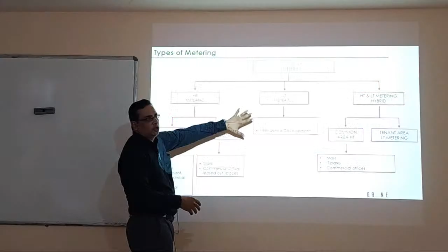I am getting my feed from outside from a supply company. I am only putting meters. I am not putting transformers inside. Much simpler for you. You don't need to give a space for transformers. But when you shift from a residential development to a commercial development, which is a mall or a hotel or a hospital or something else, you will go into this category. So it's called HT metering. HT metering would need transformers to be within the building or outside the building. That decision can be taken as per your design call, what space you have outside, what space you have inside. If you are outside, you can use oil-cooled transformers.